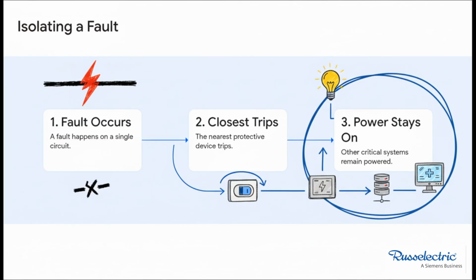When a fault happens, let's say a short circuit in a single outlet, you only want the one breaker directly protecting that specific outlet to trip, not the main breaker for the whole floor, and definitely not the one for the whole building. Everything else has to stay on no matter what. That, right there, is perfect selective coordination.